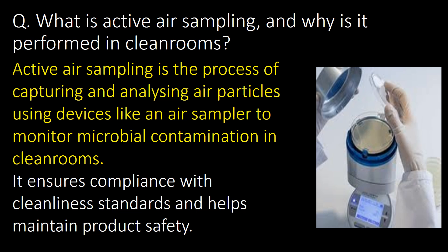Active air sampling is the process of capturing and analyzing air particles using devices like an air sampler to monitor microbial contamination in clean rooms. It ensures compliance with cleanliness standards and helps to maintain product safety.